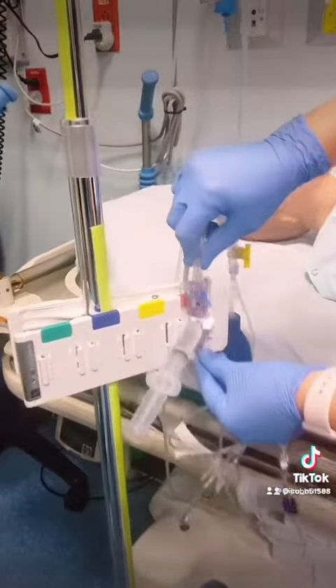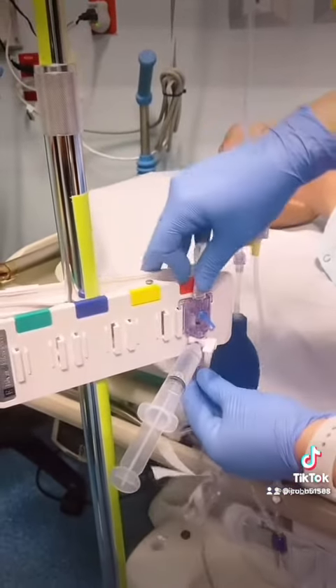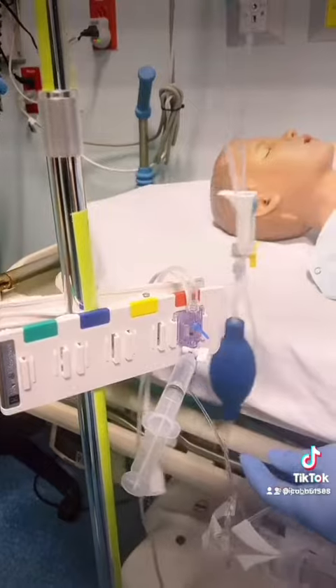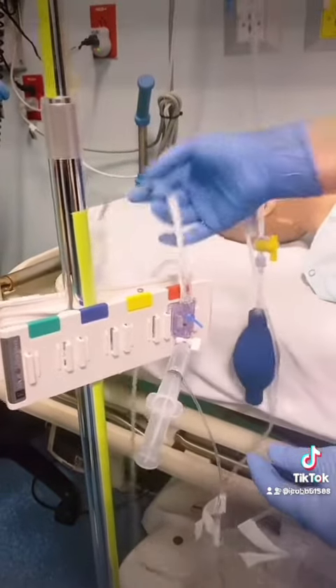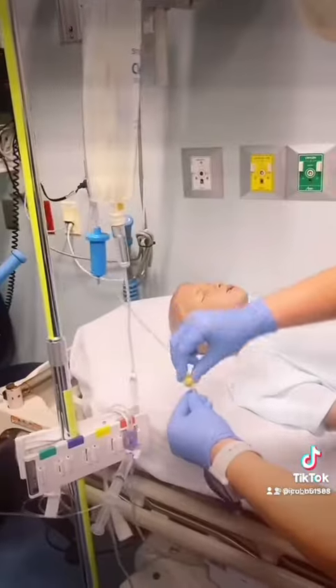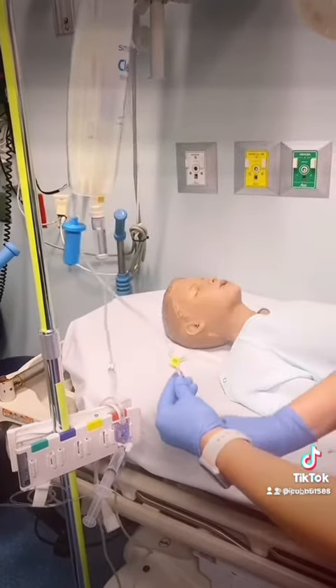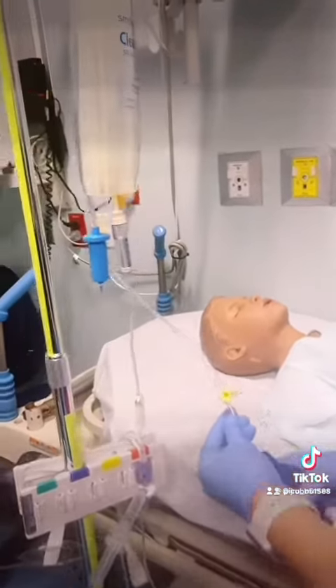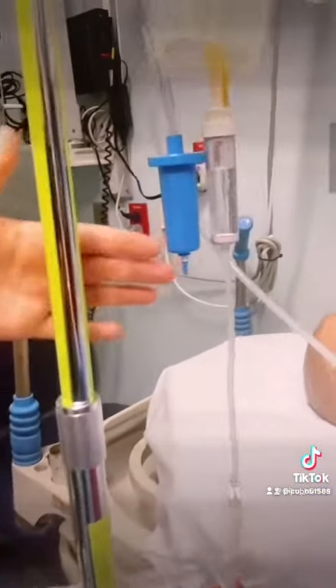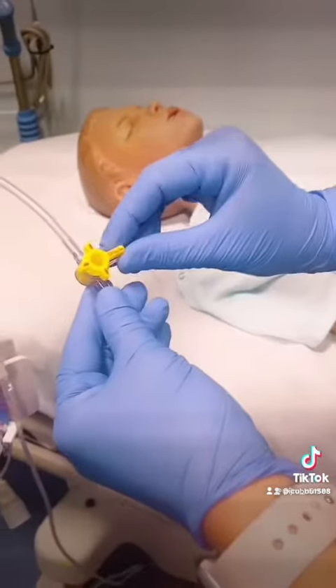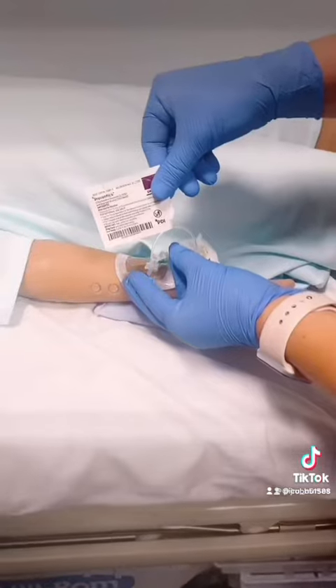Now go ahead and slide your transducer into the pole clamp, obviously in the red side for arterial line. And you want to make sure that your cables are facing up. Now inflate your pressure bag by turning the stopcock off to the port on the right and pumping manually. Pump until the little thing turns green. Then turn your stopcock off to the pressure bag. Now you're ready to connect to the patient.